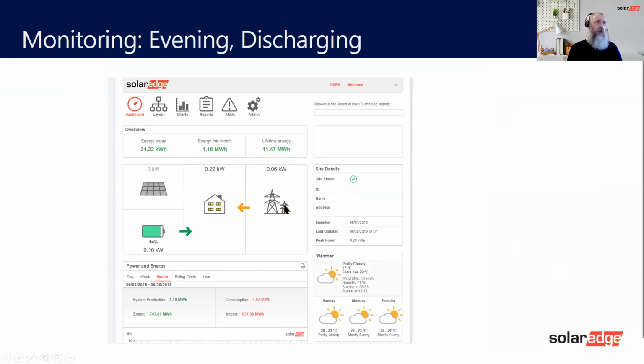This one here, you can see that the grid is also importing and the battery is now exporting. So the battery is now exporting to the actual home, but the PV is doing nothing. So there is a slight time delay in how quickly you might see that this turns on and off when you look at the dashboard. It's partly due to the time it takes the information to get from the inverter to the monitoring, and it reacts quicker than what you actually see it, to be honest.